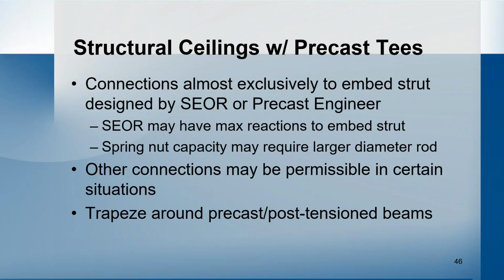There are some other connections that may be permissible in certain situations. Where we've had some interruptions in the embed strut, we've been permitted to connect to the sides of the precast tees, but the precast engineers typically have some specific parameters associated with that: where you're allowed to connect, and how deep you're allowed to connect. They've also permitted the use of their precast tee pick points as through bolt locations, which we've utilized in the past as well. And often another thing that needs to be accounted for is trapezing around your precast and post-tension beams, because those have so much post-tensioning in them that you really can't connect to them, so you need to frame around them.